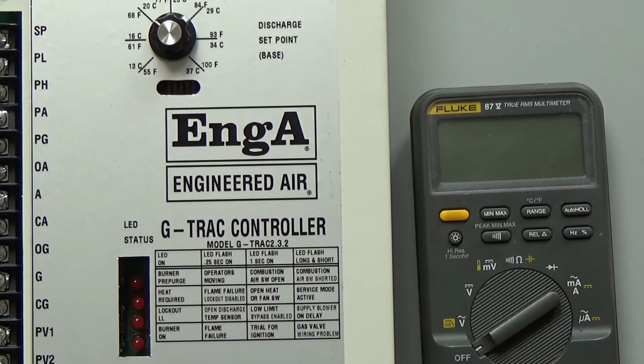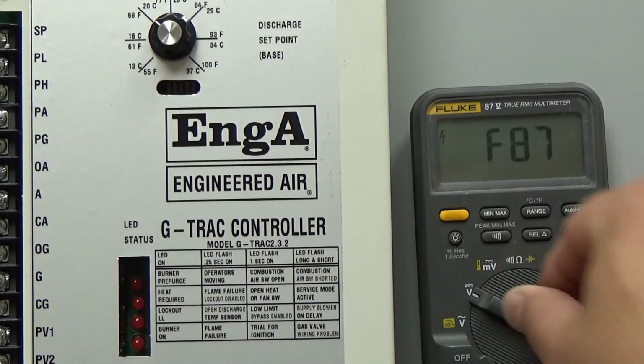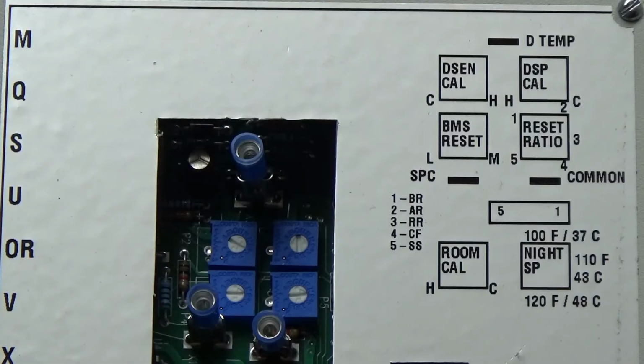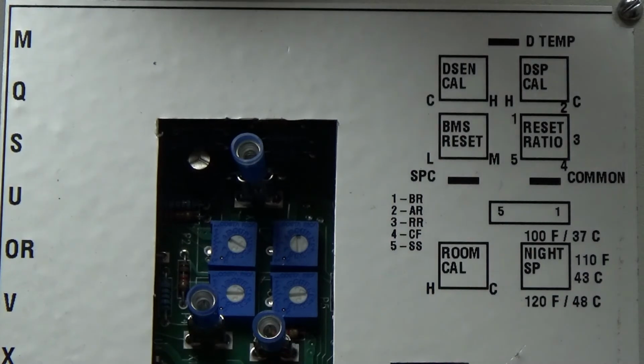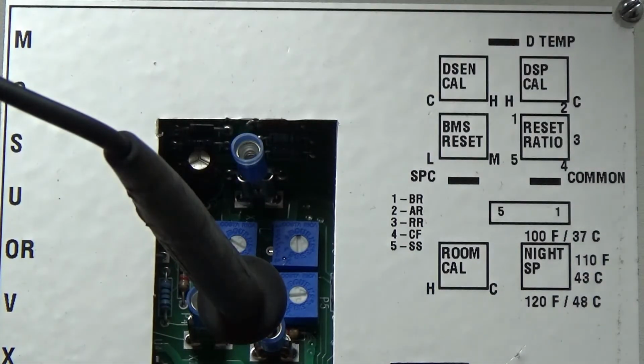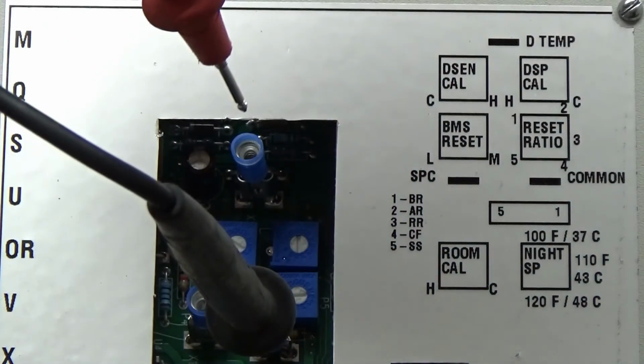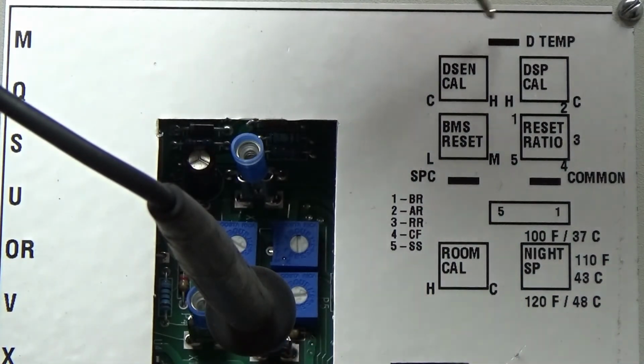To calibrate the discharge air sensor, use a thermocouple and measure the temperature at the sensor. Make sure the temperature at the sensor is steady. Next, with the GTRAC2 powered, set your multimeter to volts DC. Next, set the common lead of your multimeter onto the common test pin and the positive lead of your multimeter onto the pin labeled D temp.